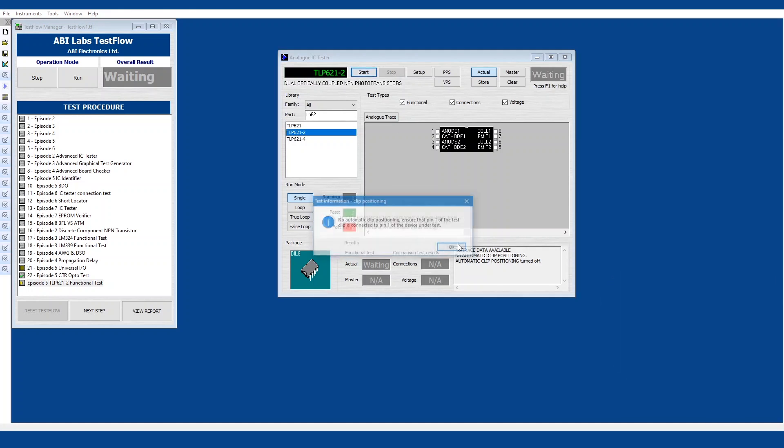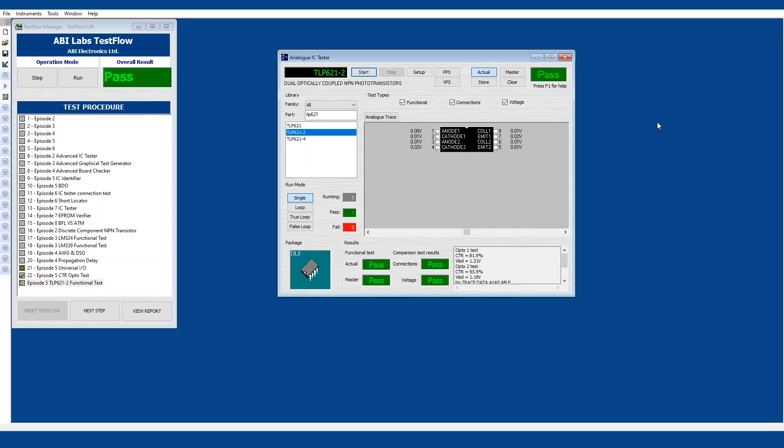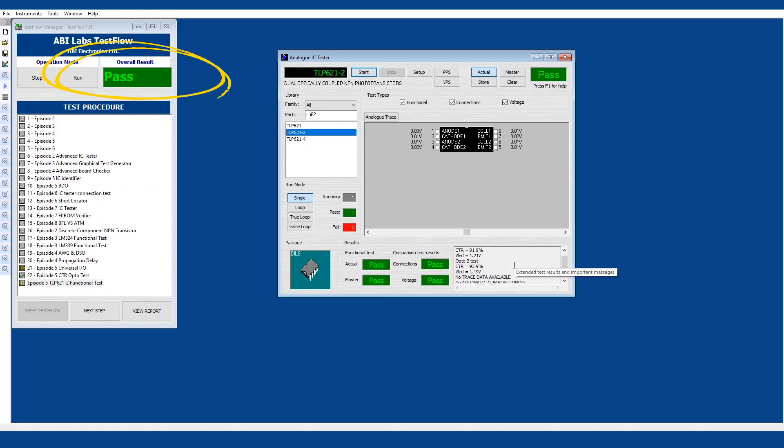So this is a power off test. Automatic clip positioning has been turned off and it will give us a pass or a fail depending on the functionality of the device. There we go, we've got a pass and it's done as we did before the CTR ratio and check that the device functions as it should.